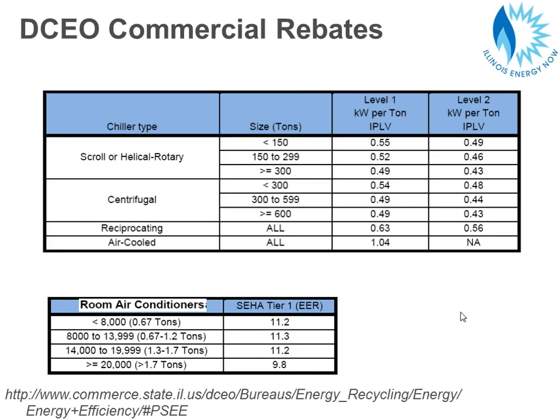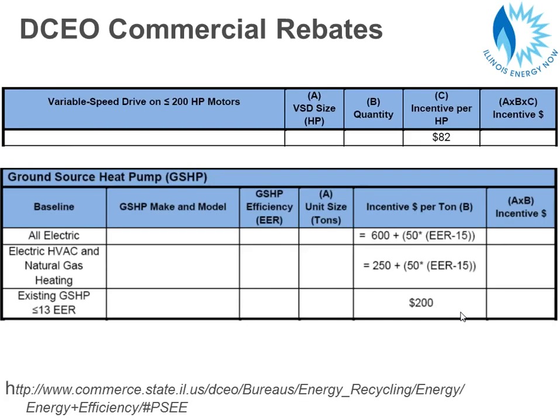And then for compressors, for chillers, these would be the target amounts. Once again, you have to know what kind of compressor you have, what the size tonnage of the machine is, and then you'll figure out what your kW per ton target is. Just like with the utility program, it's based on part load, not on full load efficiency. VFDs are similar to the ComEd program, although the incentive is $82 per horsepower, and that really does pay for the drive itself, and then you only have to pay for installation labor. That's a very, very good deal for the VFD option.